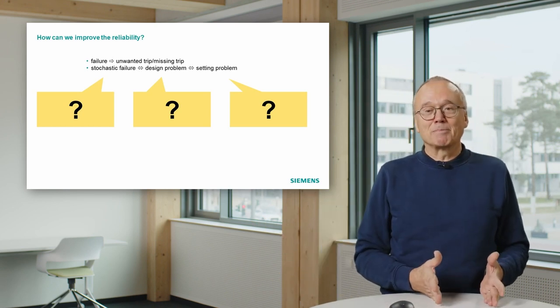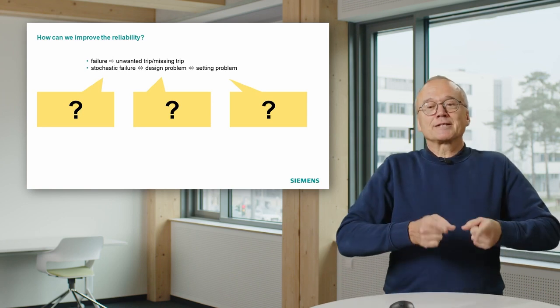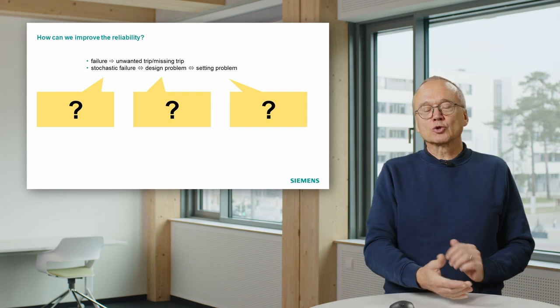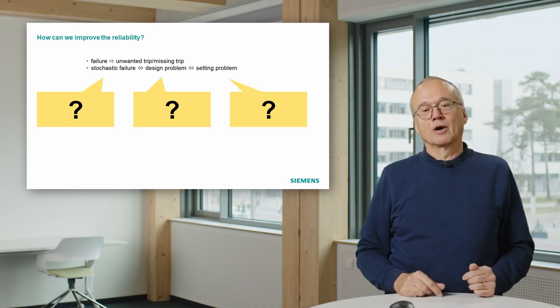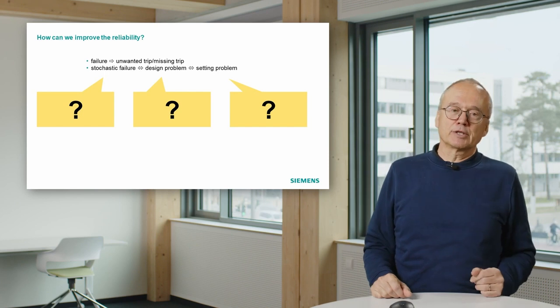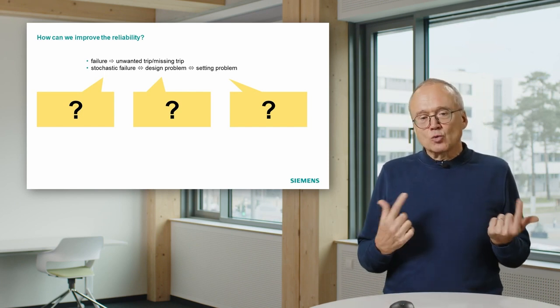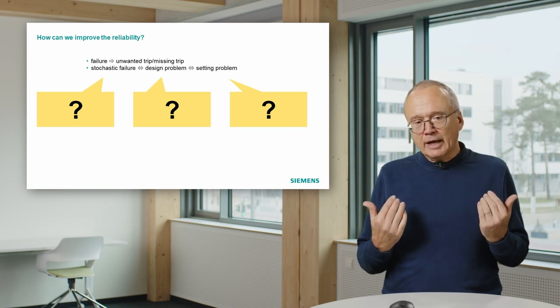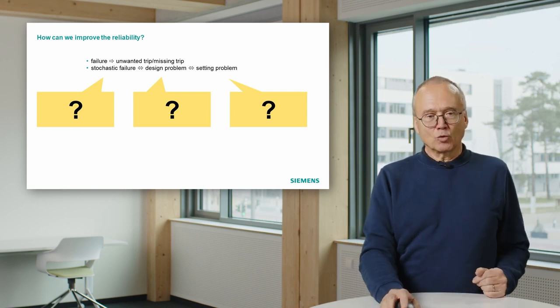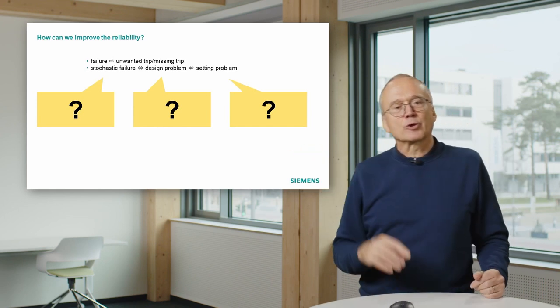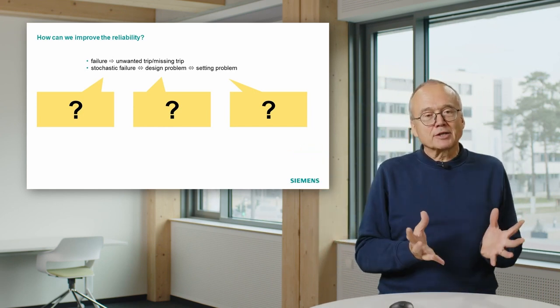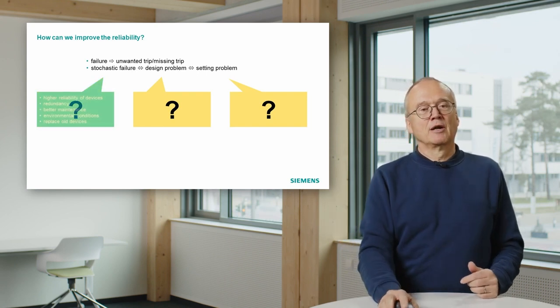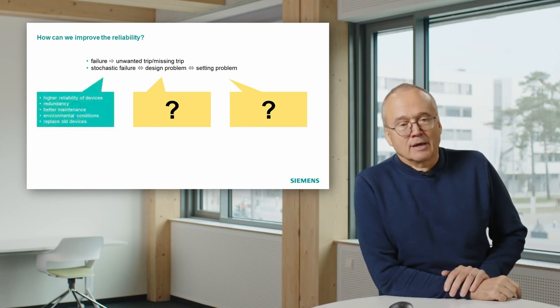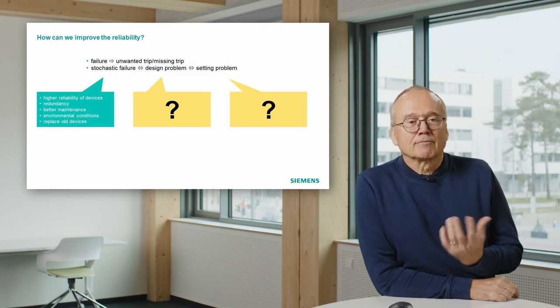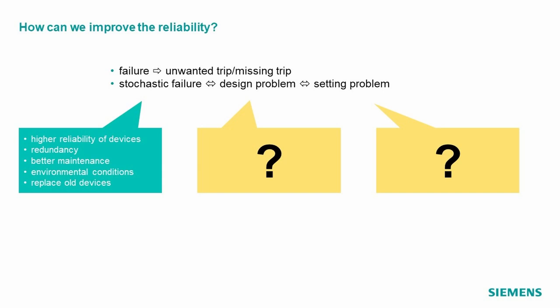And in this simple example, you see it was a wrong investment to invest all the money into the front door. You should have taken half of the money and invested it into the back door. And we have a somewhat similar situation in protection. We have to look, where do problems come from and where should we do something to improve the situation. And there we have to look at these three classes of problems: stochastic failures, design problems, and setting problems. What can we do to reduce the rate of stochastic failures? We need higher reliability of devices. That is a thing for the manufacturer.